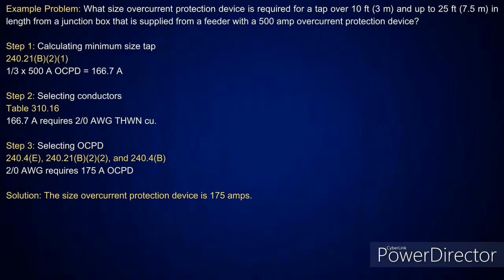Awesome. Now, if you look, this is a tap from 10 foot to 25 foot. I said all other taps, what do we take it at? A third. So I take a third of that 500 amp overcurrent device that's upstream. That gives me 166.7 amps. I go to table 310.16. The next size above that is 175 amps, which is a 2-aught conductor. Guess what? It matches up with a standard size in table 240.6(A) for the overcurrent device. So you would need at least a 2-aught, and a 175 amp overcurrent protection device would be your minimum for that 10 to 25 tap. Nice.